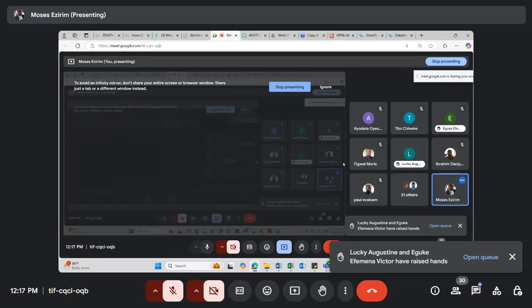So there are 6 number of batteries, how do I utilize that? Then you can't do it that way. If it's 6, then it's 24 volts that you do. If it is 48, you will need multiples of 4. So you can't do it unless you tell the client that they should buy 2 more, or you just make do with the 24 volts. Since it's residential, nothing wrong with using 24 volts.